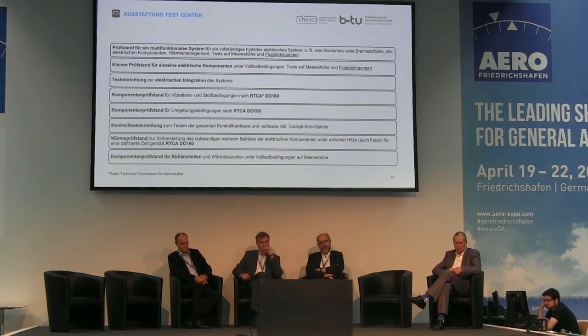There's also a small altitude chamber because it's very cost intensive to operate these things, for example to test one component, one motor, one inverter under high altitude. All the components have to go through the small test chamber to prove that they can work under these conditions before we set up the complete system test in the big test chamber.